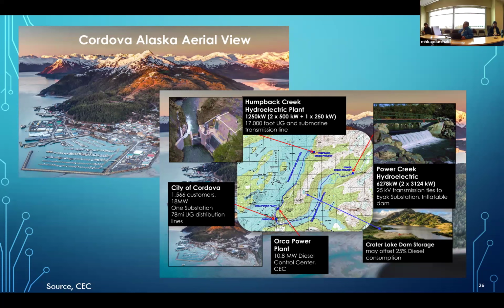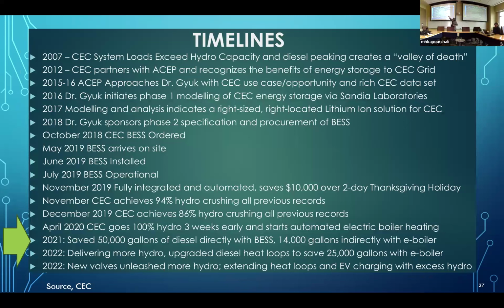So they put in a battery, made a pitch with ACEP to use a battery essentially to take over frequency control and release the hydro to convert as much water as possible to energy. That was a simple goal, stage one, and it worked. In one year, they recorded 50,000 gallons of diesel fuel reduced. This is a great example of a practice that could be implemented cost effectively, in this case supported through DOE funding. DOE helped pay for the battery energy storage system to evaluate this application. It worked well, and the battery would have paid for itself in a couple of years just on diesel fuel use reduction. It was a lithium-ion battery system sold by ABB with a SAFT battery inside.